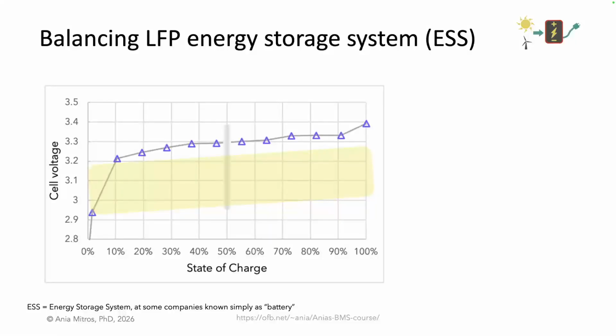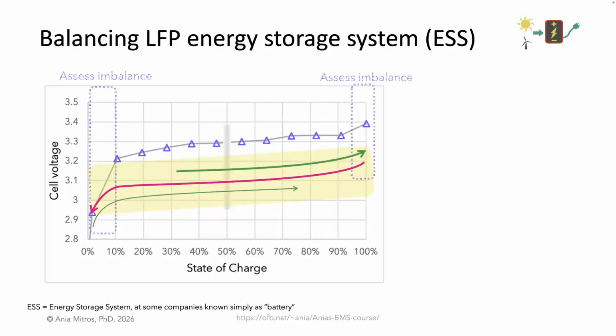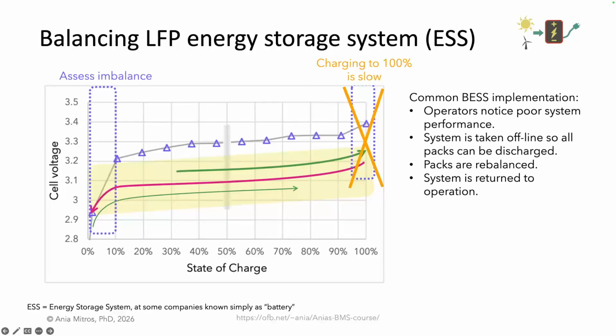To balance an LFP energy storage system battery pack, we can occasionally cycle it deeply and assess imbalance where the voltage SOC curve is steepest. Because charging to 100% is slow, in BESS applications, discharging to low state of charge is preferred. Commonly, in the BESS application, the whole system is shut down for balancing. When operators notice poor system performance, they take the whole BESS offline, the batteries are discharged, and balancing is initiated. The batteries remain at low state of charge until balancing completes, and only then the system returns to operation. I am baffled by the inefficiency of this.